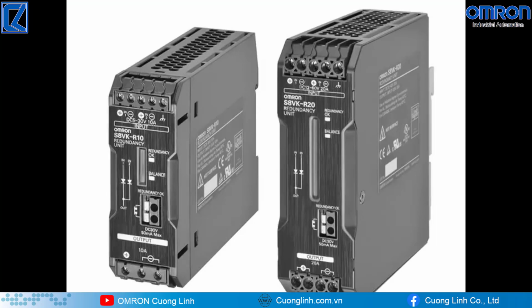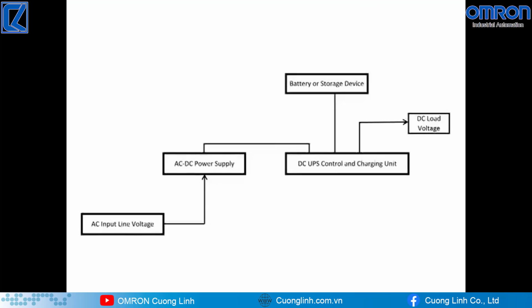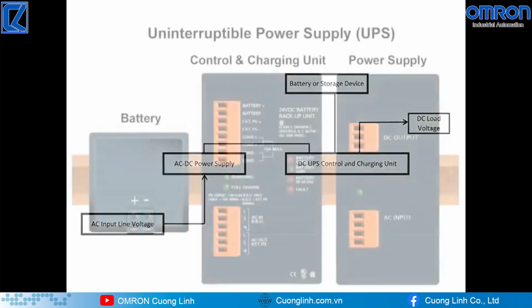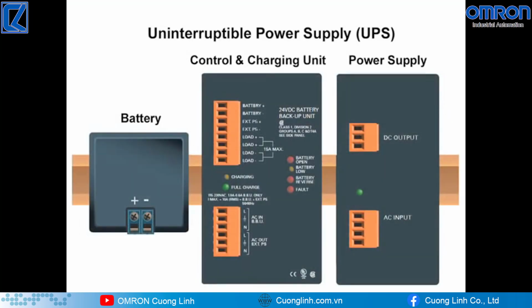The DC UPS system consists of an AC to DC power supply, a UPS control unit, and a lead-acid battery. These three parts can help provide power up to 40 amps for 30 minutes, depending on the size of the lead-acid battery. This system will continue to operate when there is a power outage, but may not provide power if one of the three parts fail. The system will operate until the computer can properly save or safely shut down the equipment.